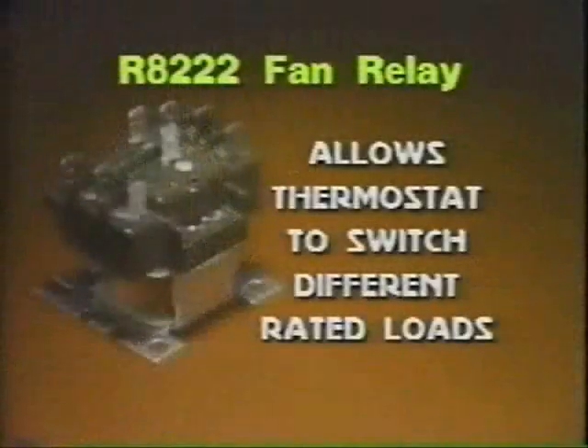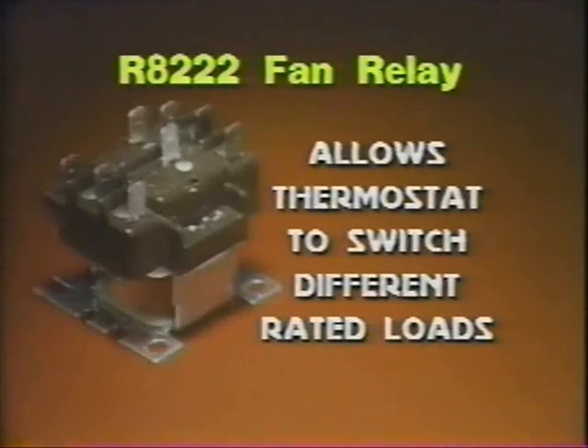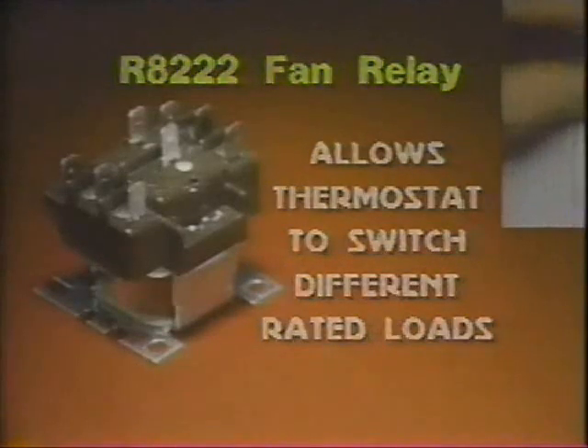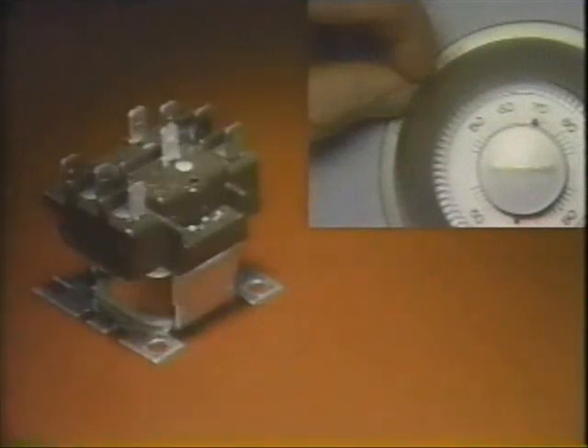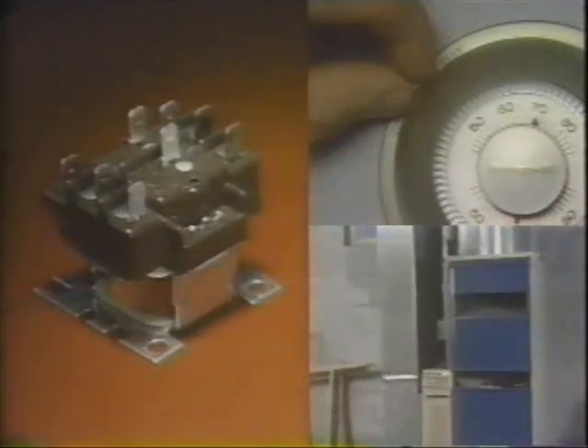Contactors, which are basically big relays, are normally used for compressor switching in larger systems. Fan relays make it possible to control fan operation with a thermostat that is not rated for direct switching of the load. In a typical system, a call for cooling from a 24-volt thermostat energizes the fan relay coil. Then the contacts pull in and activate the 120 or 240-volt circuit for the indoor fan, turning the fan on or switching it to a higher speed.